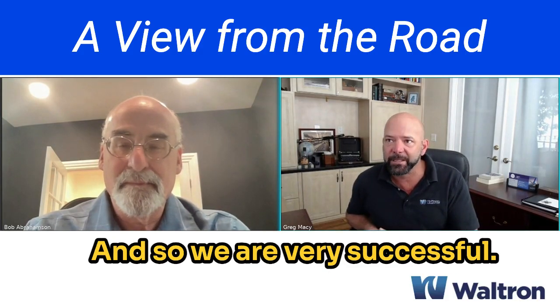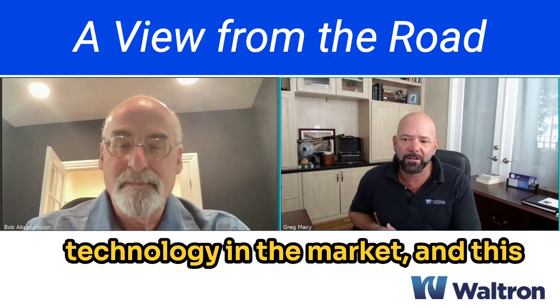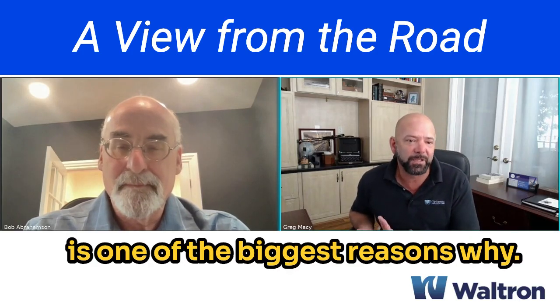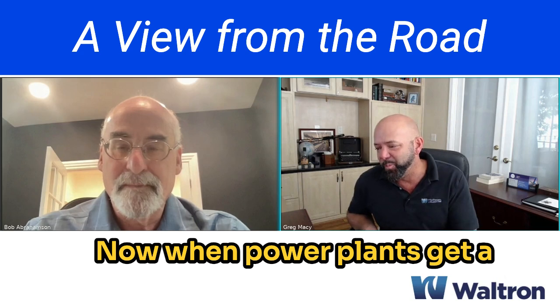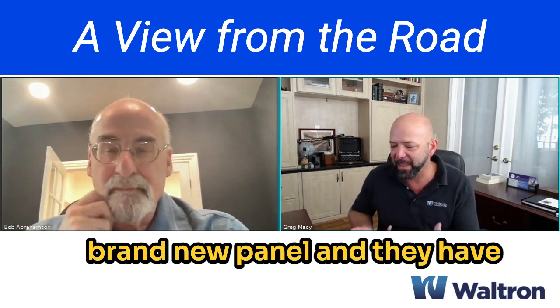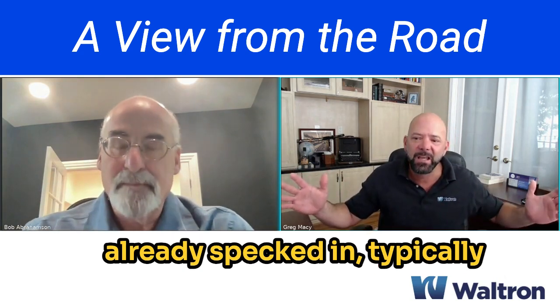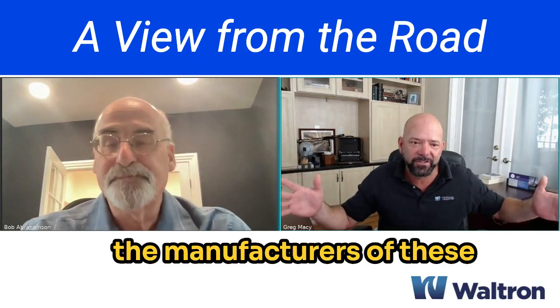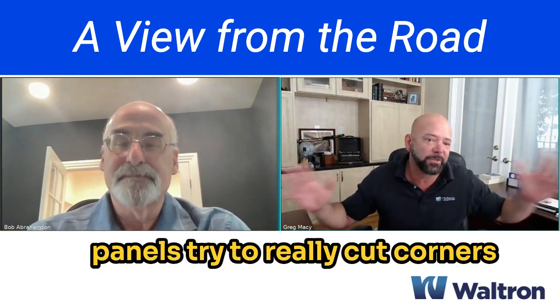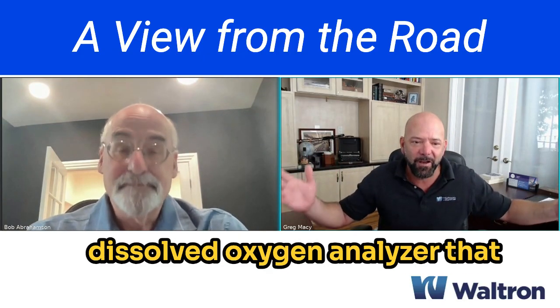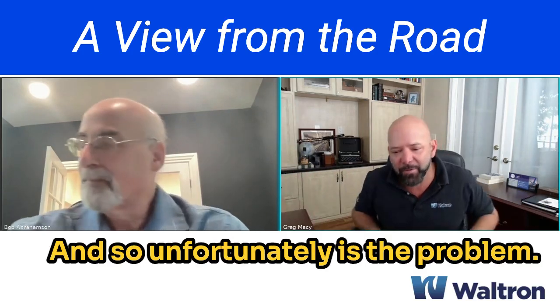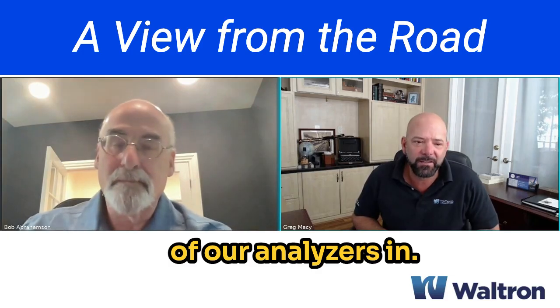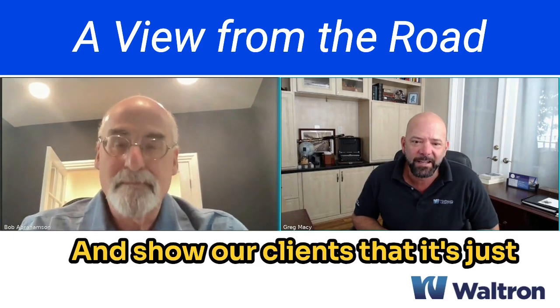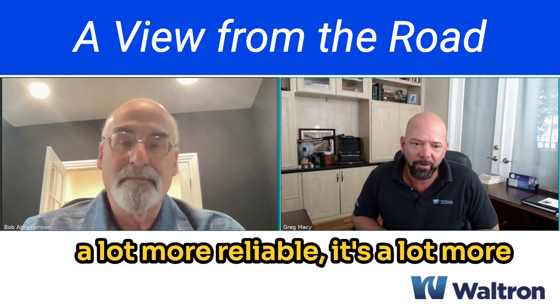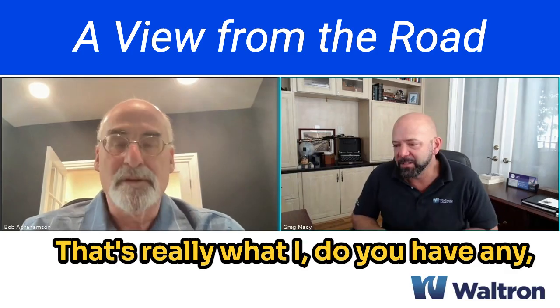We are very successful - we're the leaders in LDO technology in the market, and this is one of the biggest reasons why. When power plants get a brand new panel with instrumentation already spec'd in, typically the manufacturers try to cut corners and put on the cheapest dissolved oxygen analyzer they can find. Unfortunately, that's the problem. As soon as we put one of our analyzers in and show clients it's a lot more reliable and robust, it's just a no-brainer.